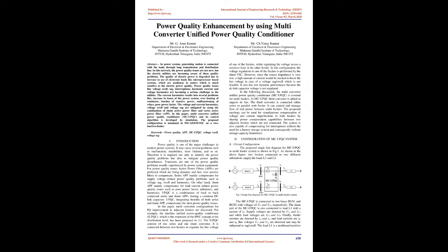In this paper, multi-converter configurations for PQ improvement in adjacent feeders are discussed. For example, the Interline Unified Power Quality Conditioner, IUPQC, which is the extension of the IPFC concept at the distribution level, has been proposed in one. The IUPQC consists of one series and one shunt converter. It is connected between two feeders to regulate the bus voltage of one of the feeders, while regulating the voltage across a sensitive load in the other feeder.